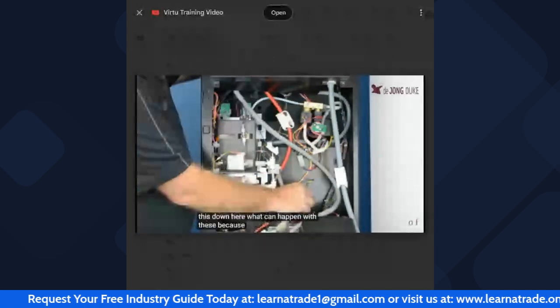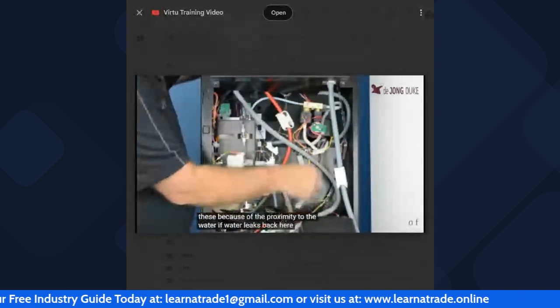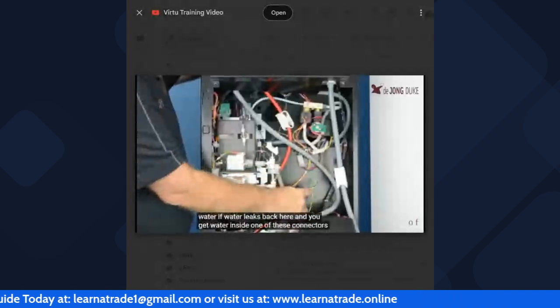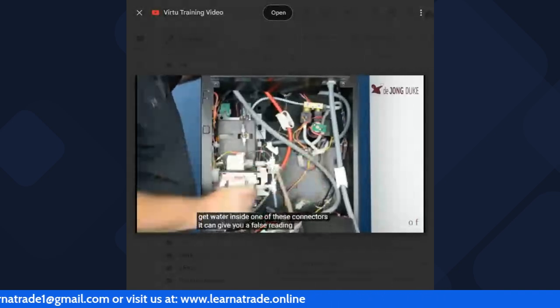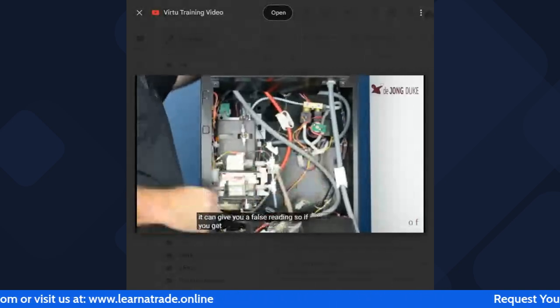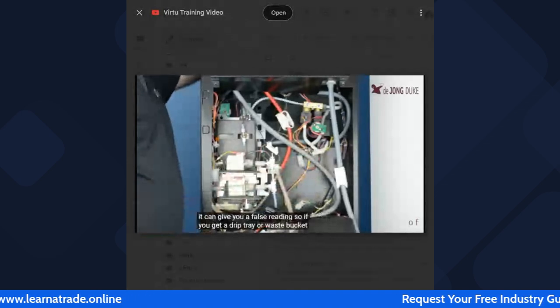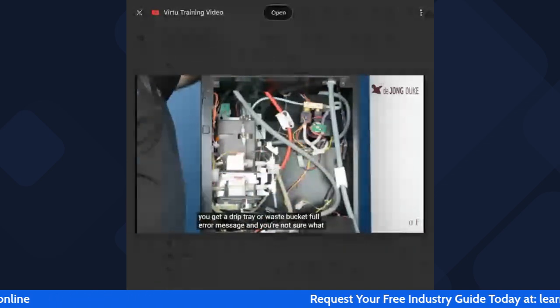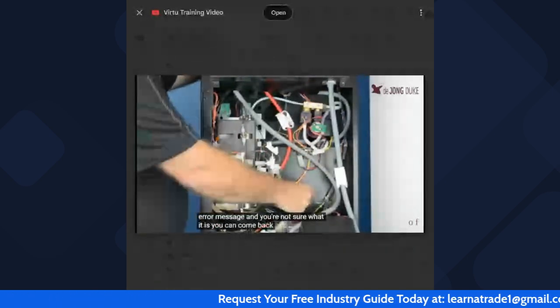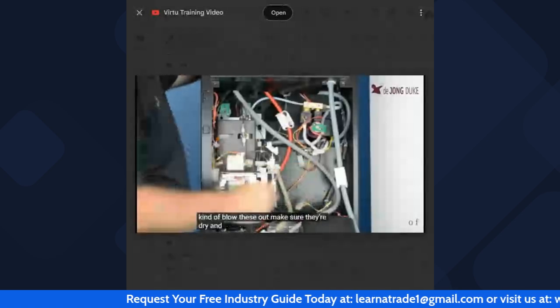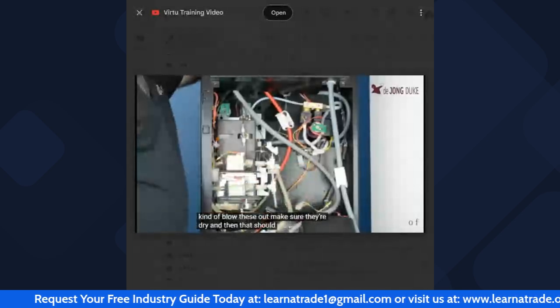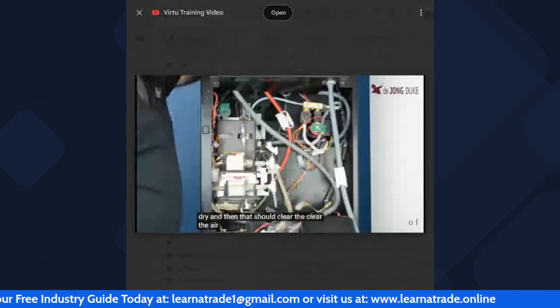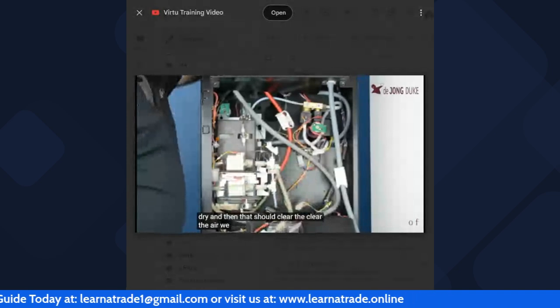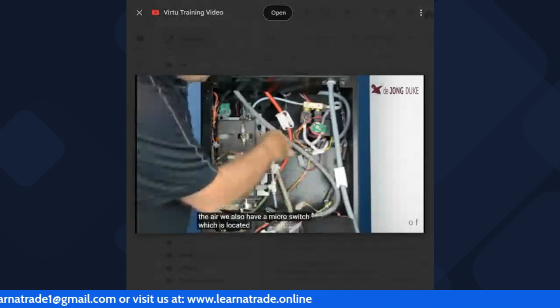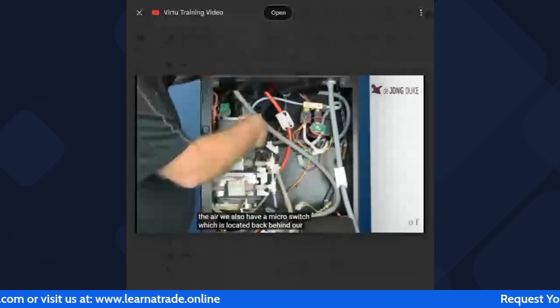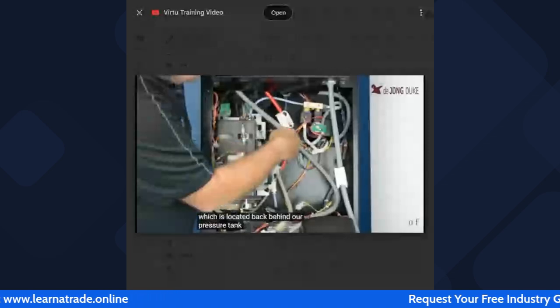What can happen with these, because of the proximity to the water, if water leaks back here and you get water inside one of these connectors, it can give you a false reading. So if you get a drip tray or waste bucket full error message and you're not sure what it is, you can come back here and just blow these out, make sure they're dry, and then that should clear the error. We also have a micro switch, which is located back behind our pressure tank.